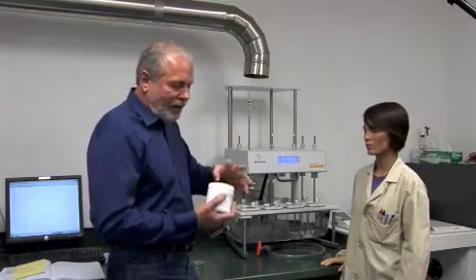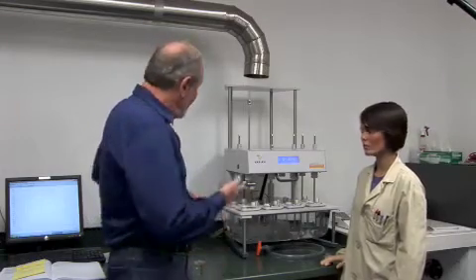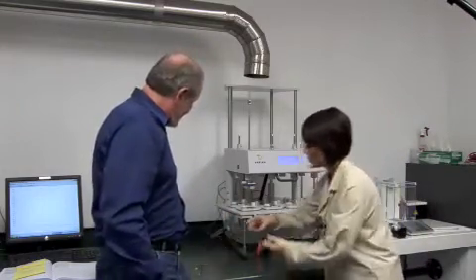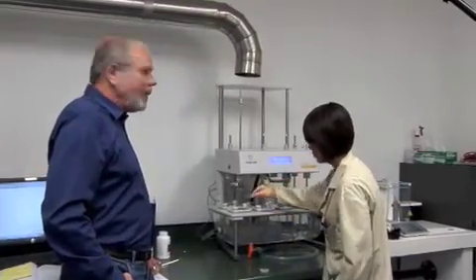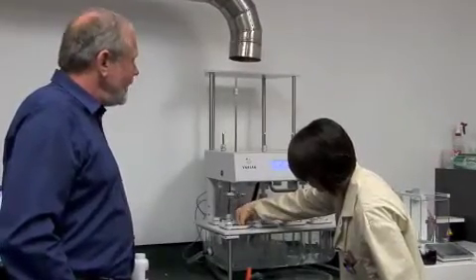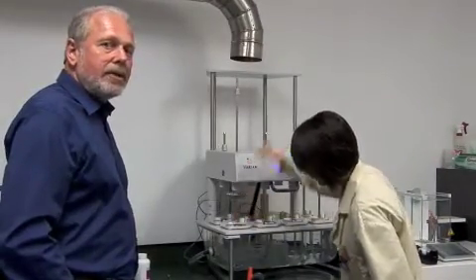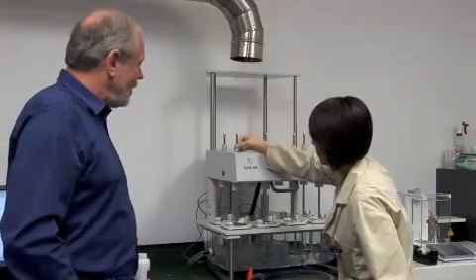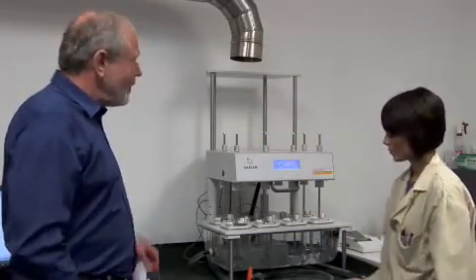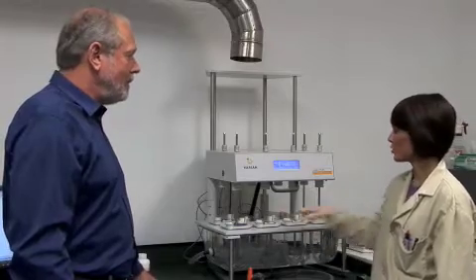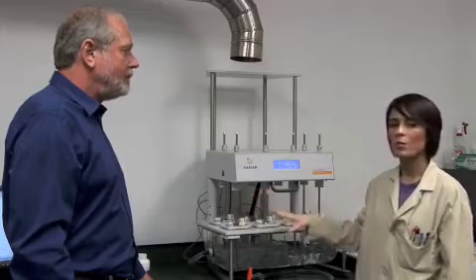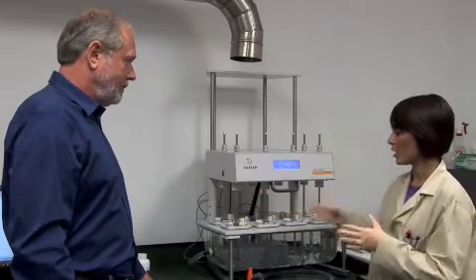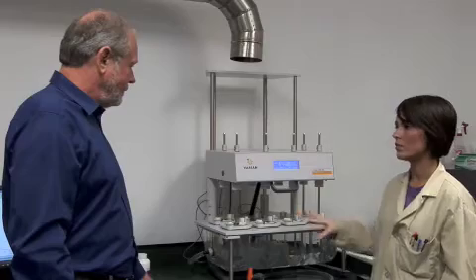Keanu's going to do the experiment, and we'll come back later once it's going and see how it goes. This machine actually simulates the human stomach, and it's the USP dissolution procedure that's called for by pharmaceutical companies. We have a total of six chambers, and they allow us to take the maximum amount of data to get a comprehensive look at what these products are.